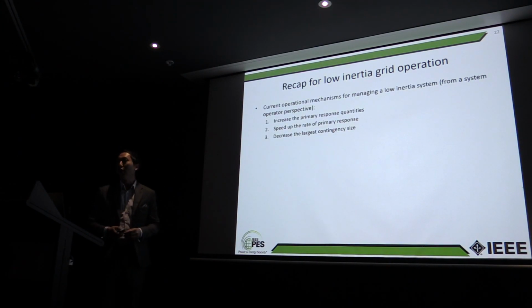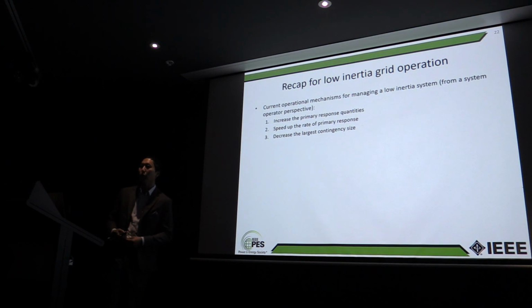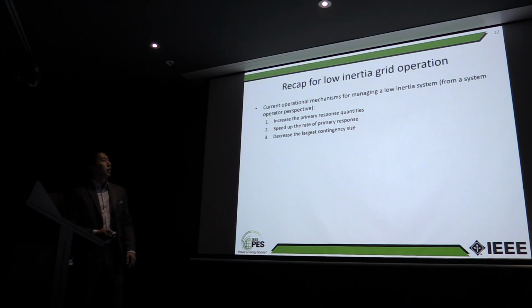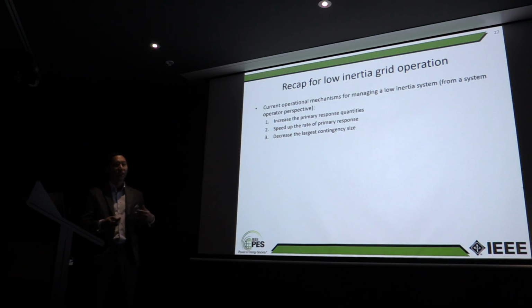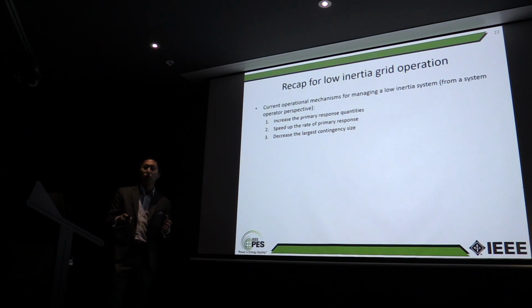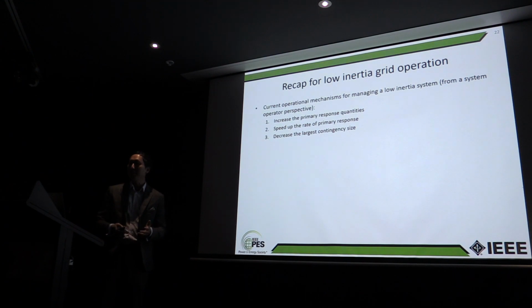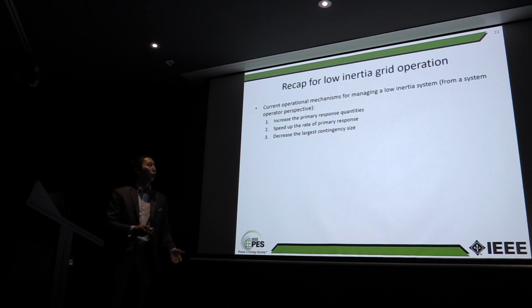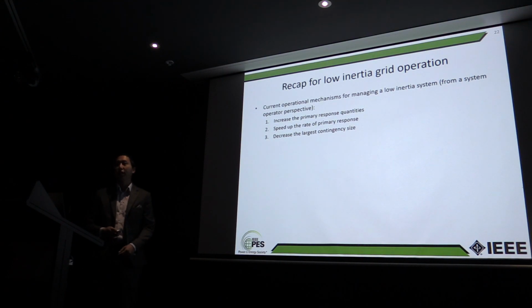So here's a recap for how we operate the system with low inertia. Here are our current operating mechanisms for how we manage the system. So this is from our AEMO or system management perspective here. We can either increase the quantities of the primary response, we can speed up the ramp rate of all these responses, or provision machines that are fast acting, or add batteries and so forth. Or we can decrease the largest contingency size. So they're the levers that we can pull right now.